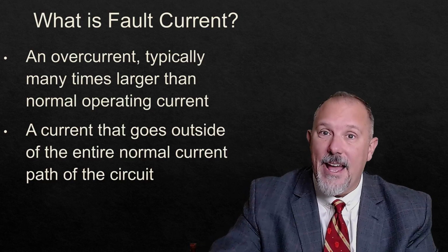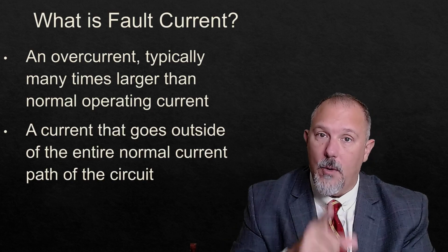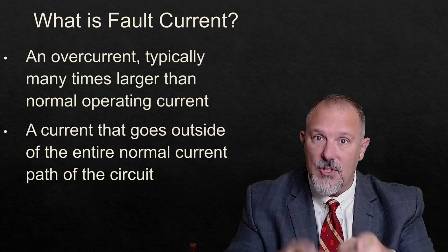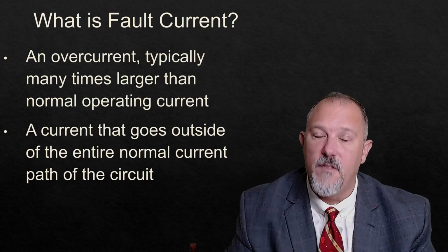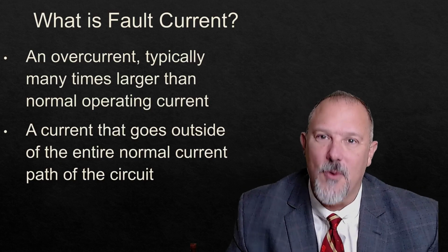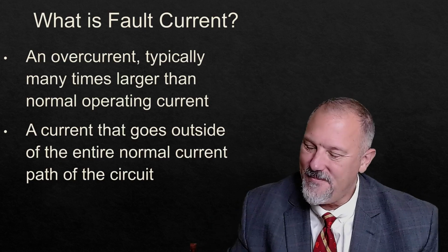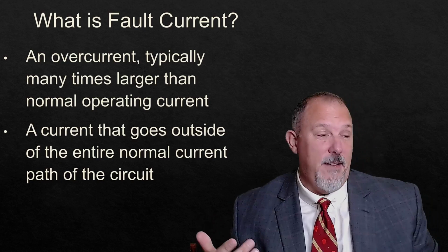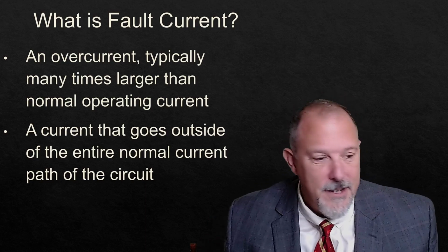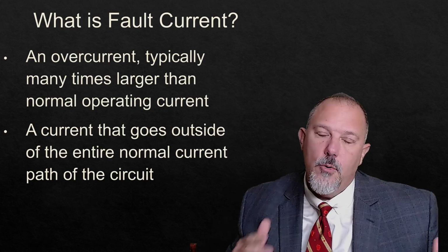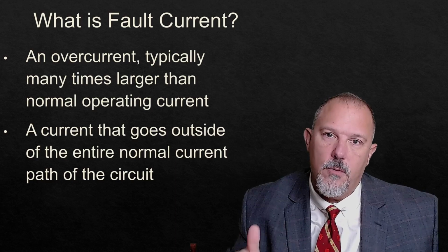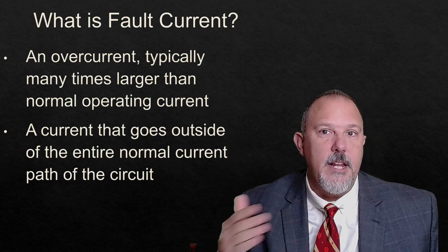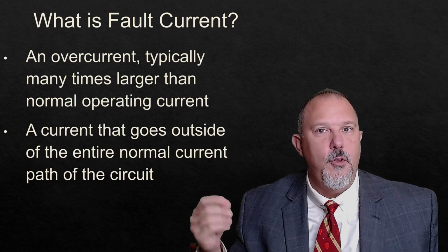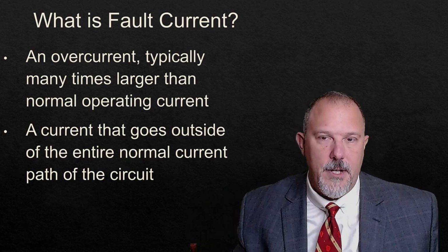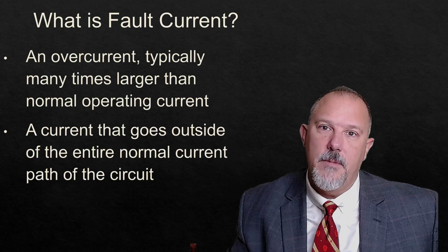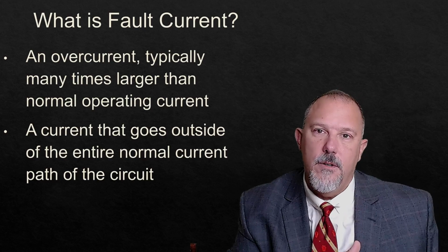And if it was an actual fault current, you could, if you wanted to, estimate, and we'll show you how to do this, how much fault current would have been drawn to that problem. Flown. Did you ever see fault current fly? I haven't seen them fly. I've seen pigs fly, but never fault current.